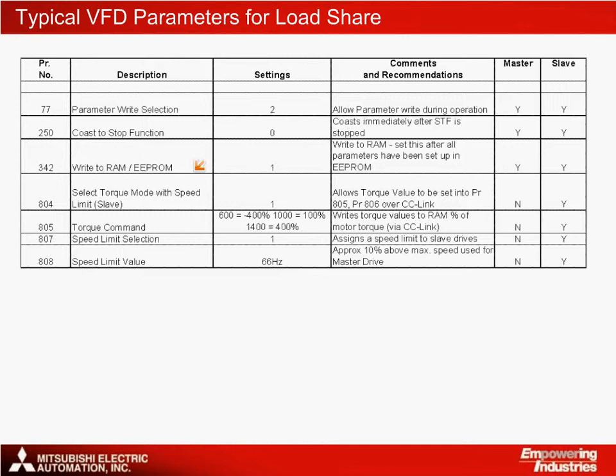Writing to RAM instead of EEPROM enables continuous changes to be made to the speed and torque settings without damaging the drives. Parameters 804 to 808 put the drive into torque or speed mode and are set according to whether the drive is a master or a slave.